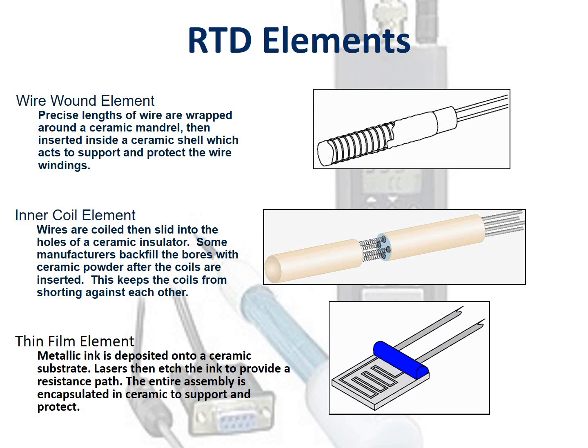In the inner coil element RTD, wires are coiled then slid into the holes of a ceramic insulator. Some manufacturers backfill the bores with ceramic powder after the coils are inserted to keep the coils from shorting against each other. In the thin film element RTD, metallic ink is deposited onto a ceramic substrate. Lasers then etch the ink to provide a resistance path, and the entire assembly is encapsulated in ceramic to support and protect it.